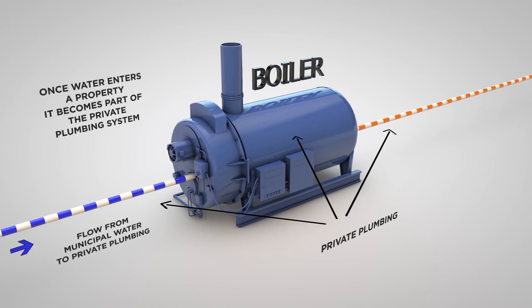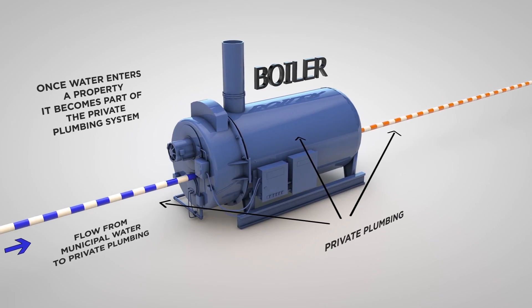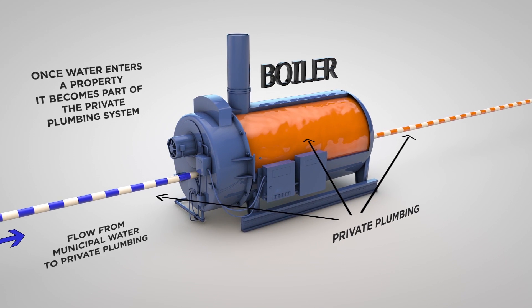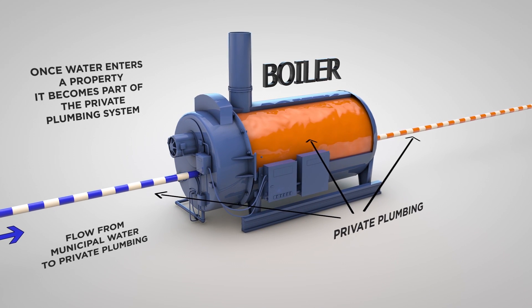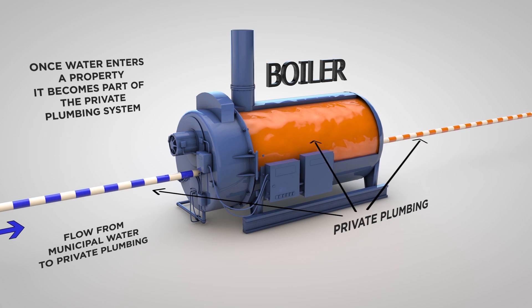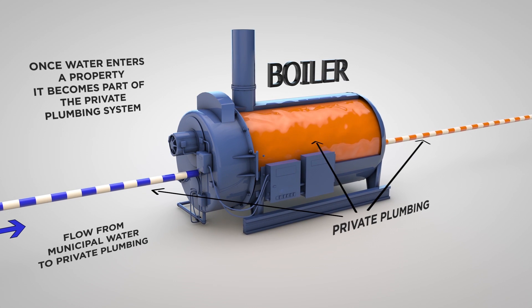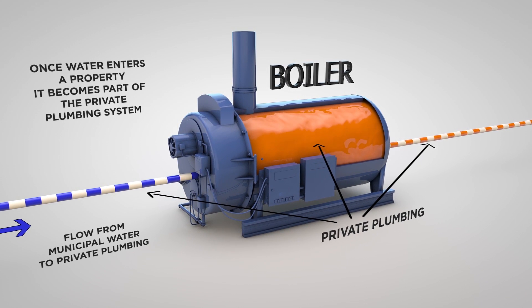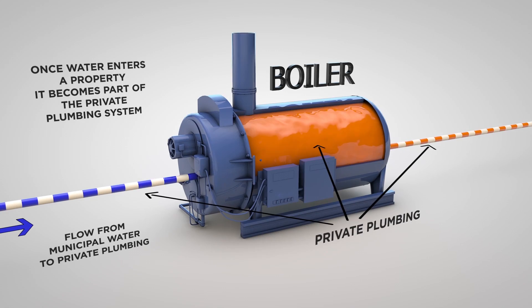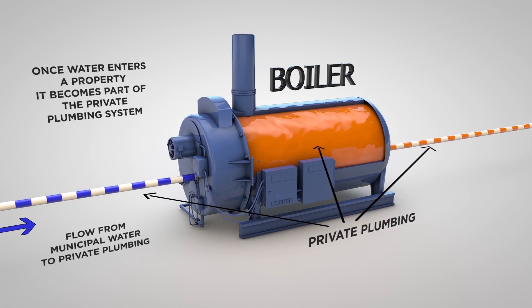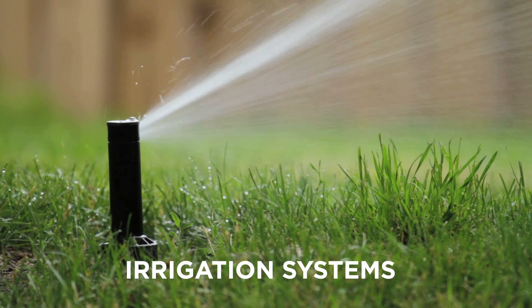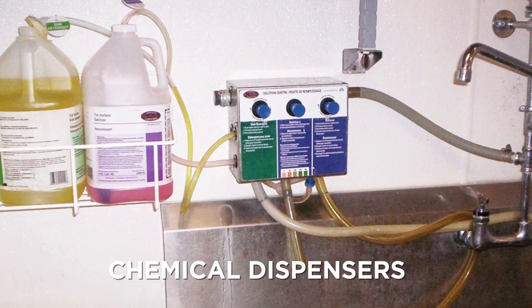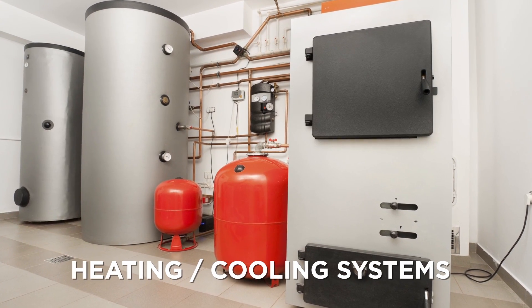A cross connection is a direct or indirect connection between the drinking water system and any other liquid, gas or other substances. In a direct cross connection, there is a physical connection between the drinking and non-drinking water system, such as an underground sprinkler system, chemical dispenser, or heating and cooling system.